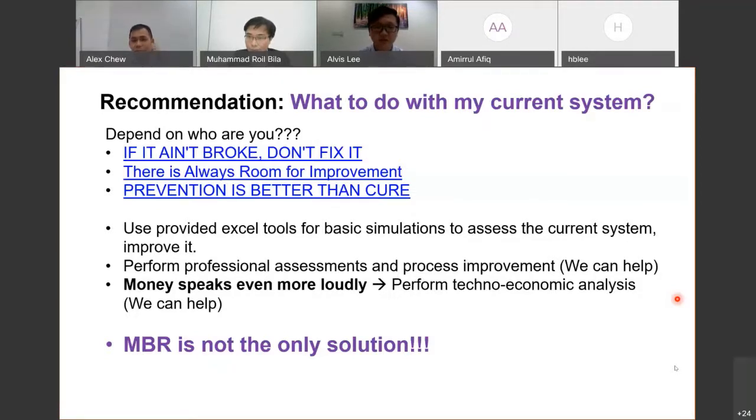Thank you, Mr. Roy. So the next question is from Ahmad Fazli. His question is, what are the materials for the membrane? Okay, there are so many types of membrane available. In terms of shape, you can have hollow fiber, tubular, or plate and frame. As for the material, the most common one used is polymer. The less common one is ceramic membrane. Ceramic membrane is still quite expensive, probably 20 times more expensive than polymeric membranes. So I can say more than 90% of MBRs now use polymeric membranes.